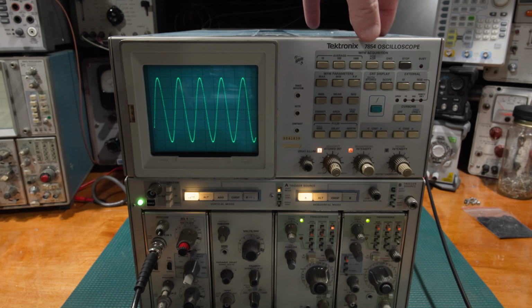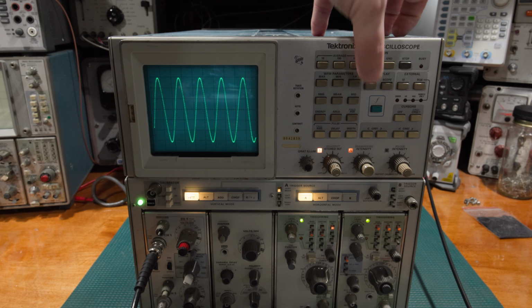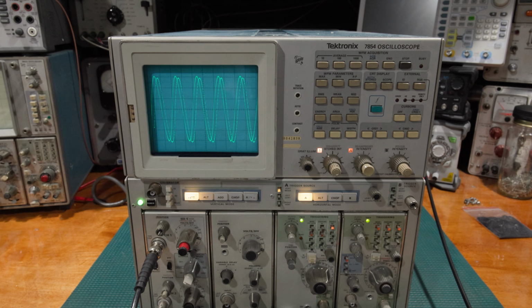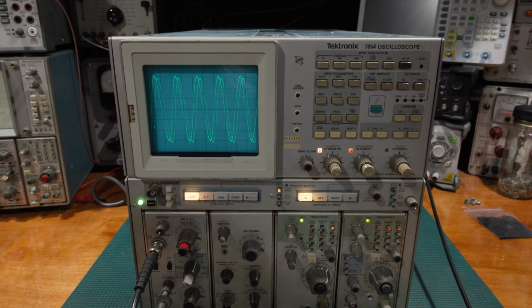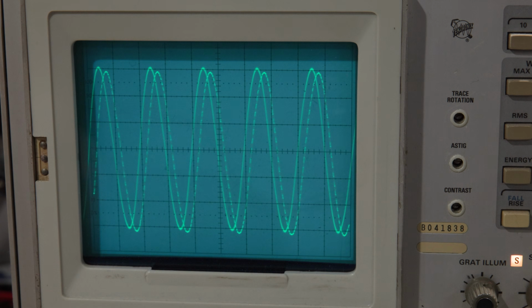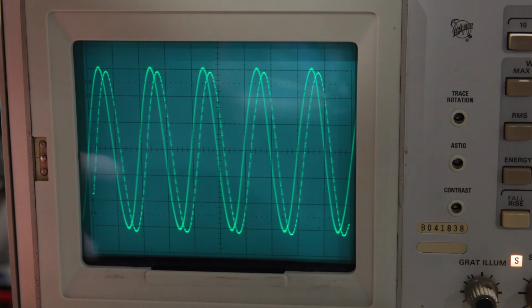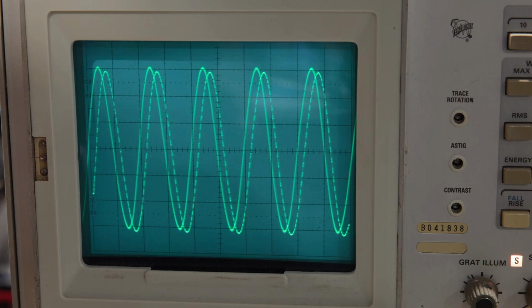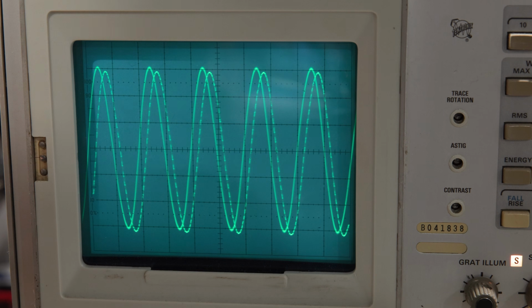Everything looks good, but if I overlay both, we can see they are off and do not line up. We'll zoom in on that. Essentially, these waveforms should be as close as they possibly can to overlapping each other. It's off a little bit, but it's off enough where the measurements that this system can take would be somewhat of a problem. So that's a quick test to see if your scope needs alignment.